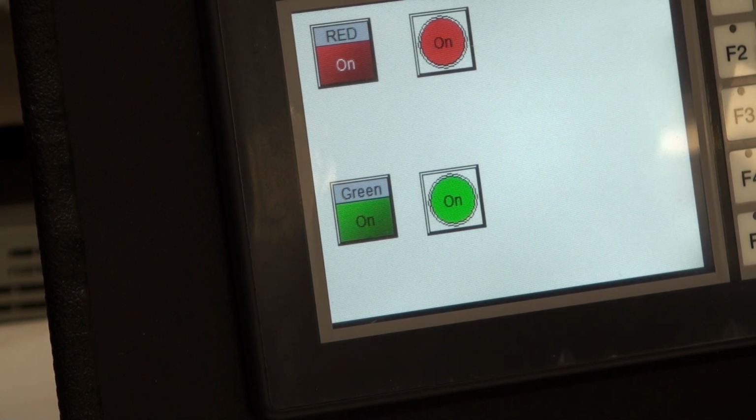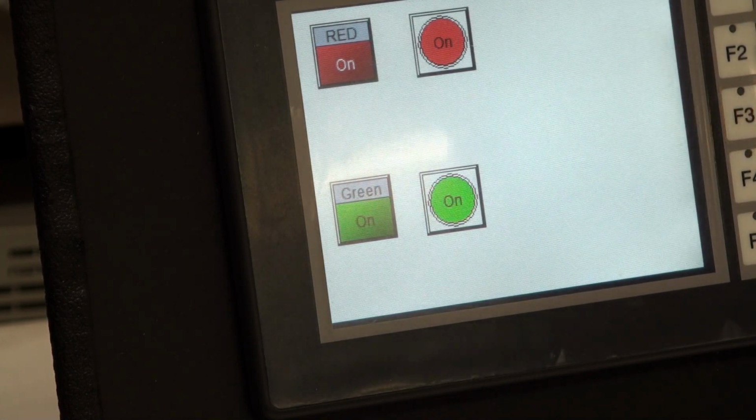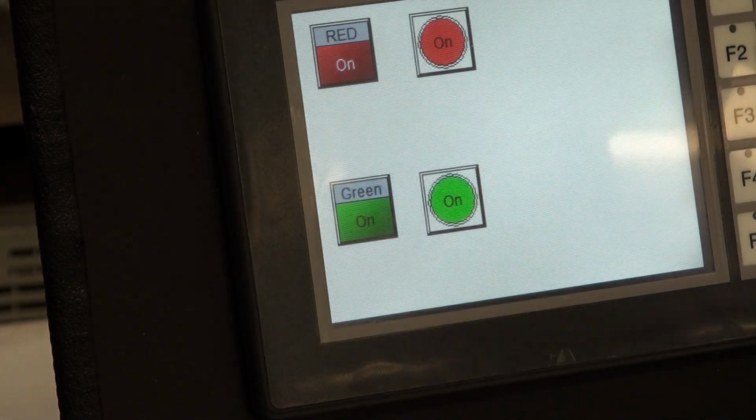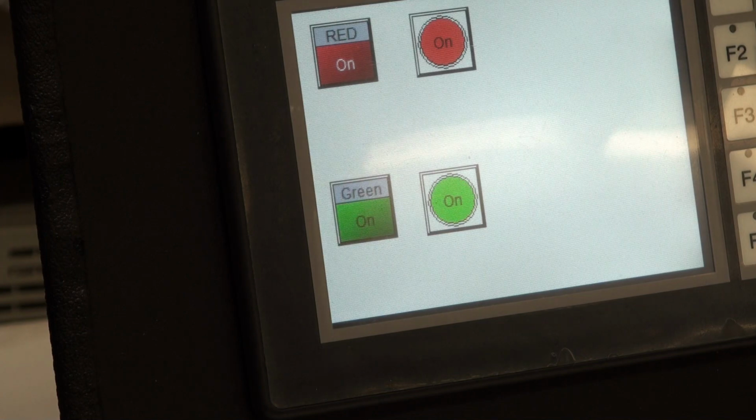If we're starting new, it's really just as easy as if we're adding in. But the very first thing we've got to do is decide what we want to do with the HMI. And I'm going to give you some kind of exercise similar to this to do. In this case, we just wanted to turn on a red output with a virtual button and a green output with a virtual button, and it made sense that those virtual buttons were red for red and green for green. And we want to know if that happened on the HMI, because one reason for doing this is it may be something an operator can't visibly see, but they need to know it's got power applied to it. So we can actually tie an output to a visual indicator on the HMI.